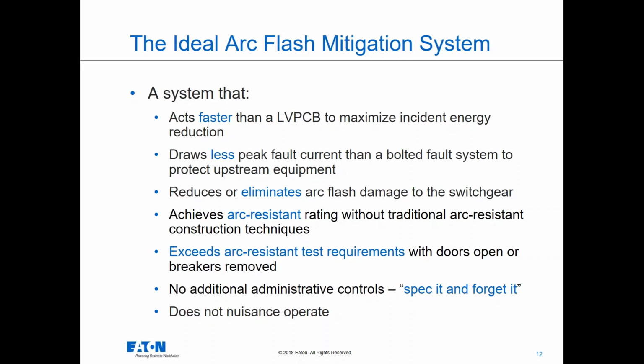And then lastly, all of the systems that have some sort of detection method to date have administrative controls. You are forced to turn on an emergency or arc energy reduction mode. You need to turn on a maintenance mode. Somebody needs to write an MOP to know that when I'm working on downstream gear X or motor control center Y, I need to go upstream to a particular breaker and turn on or somehow enable whatever the system is. It'd be a lot nicer for customers and clients to be able to walk in and know that the equipment is already protected. So from a consultant standpoint, it'd be like spec it and forget it. If it shows up and it's there, it's always working and it's always protecting the customer.